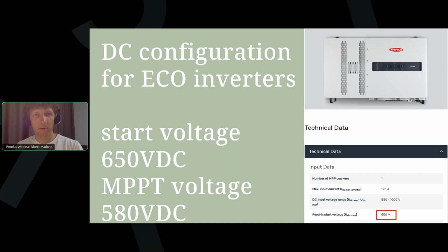Another thing is with Fronius Eco inverters, our old snap inverters with screen, and the Tauro Eco. The starting voltage installed from the PV module side is usually set too low. For these inverters, the starting voltage is 650 volts, which is quite high, so be sure you install enough PV modules for these inverters.